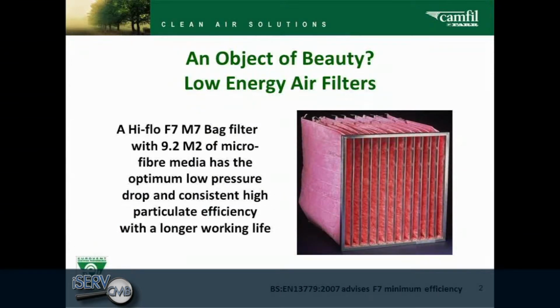And because it has so much media, it will also tend to last 2 to 3 times as long as what we call a commodity filter, which may only have 6 pockets with 380mm long pockets instead of 635. And that will mean it only has 2.9 square meters of media, as opposed to this one, which has 9.2, over 3 times as much. So you have here something that costs a relatively small amount of money, but the use of energy throughout its working life will typically be 10 to 20 times greater.